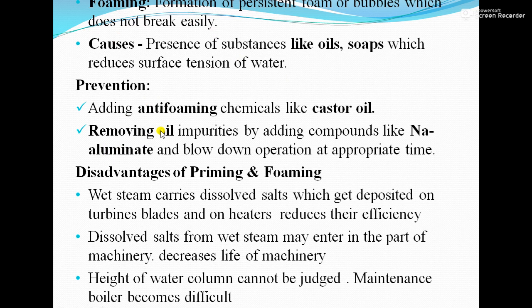Disadvantages of priming and foaming: first, wet steam carries dissolved salts which get deposited on turbine blades, reducing the efficiency of the boiler. Second, dissolved salts from wet steam may enter parts of the machinery, decreasing the life of the machinery. Third, due to priming and foaming, the actual height of the water column cannot be judged, making maintenance of the boiler difficult.